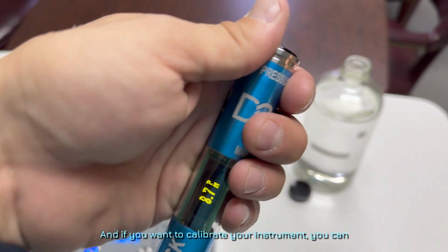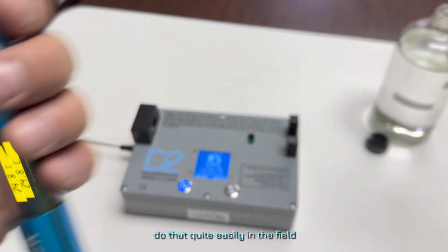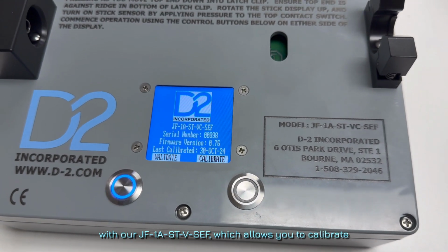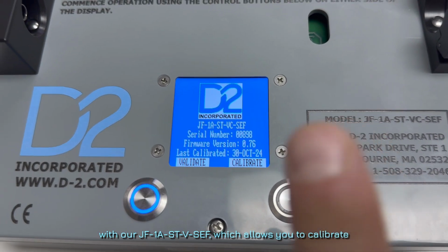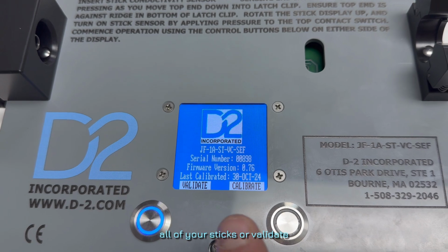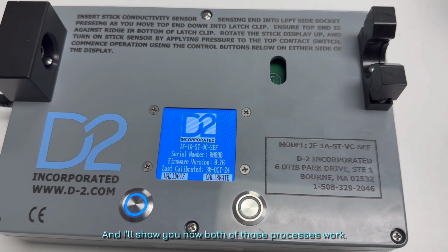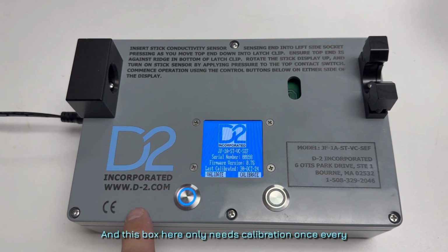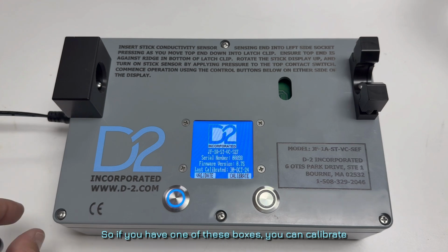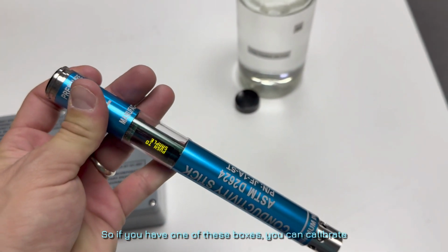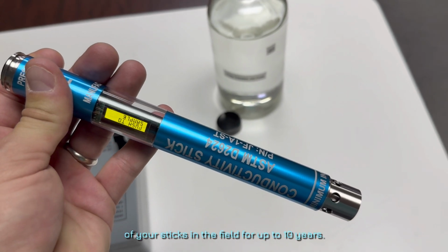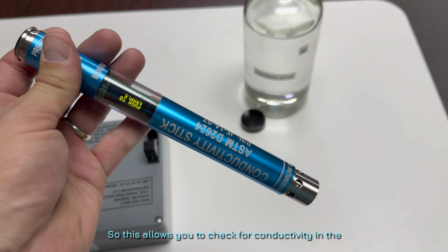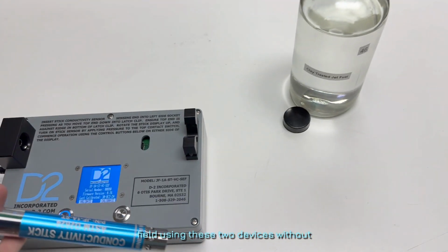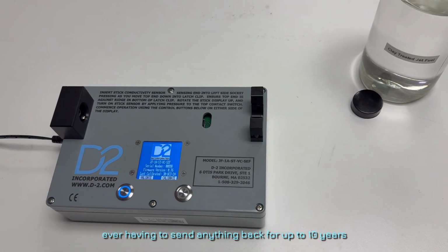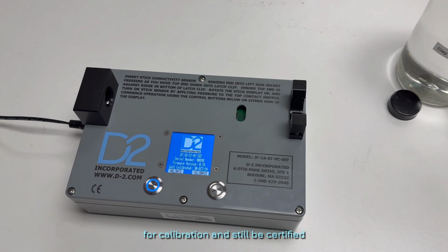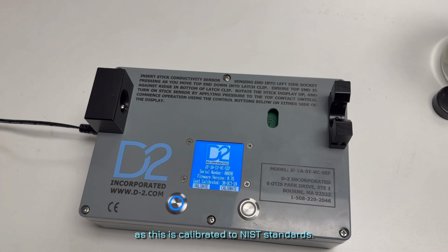And if you want to calibrate your instrument, you can do that quite easily in the field with our JF1A ST VC SEF, which allows you to calibrate all of your sticks or validate, depending on what you want to do. And I'll show you how both of those processes work. And this box here only needs calibration once every 10 years. So if you have one of these boxes, you can calibrate and verify the calibration of any of your sticks in the field for up to 10 years. So this allows you to check for conductivity in the field using these two devices without ever having to send anything back for up to 10 years for calibration, and still be certified as this is calibrated to NIST standards.